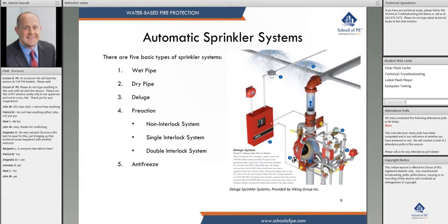Or if the hazard is so high that we have to switch to a deluge system. A dry pipe system has pipes filled with air and nitrogen. When a sprinkler fuses, the air and nitrogen release from the system and then the dry pipe valve opens, letting water into the system.